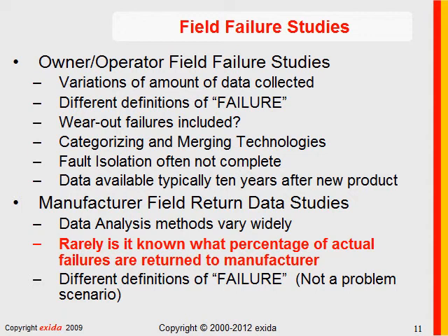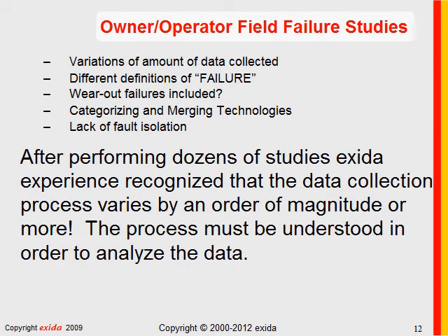Now, the manufacturer field return data have pluses and minuses also. Data analysis methods vary widely. Rarely is it understood what percentage of actual failures are returned to the manufacturer, and manufacturers have very different definitions of failures. That does not mean that both of these data sets are no good. In fact, both of these data sets have an amazing amount of useful information if you can go get it.